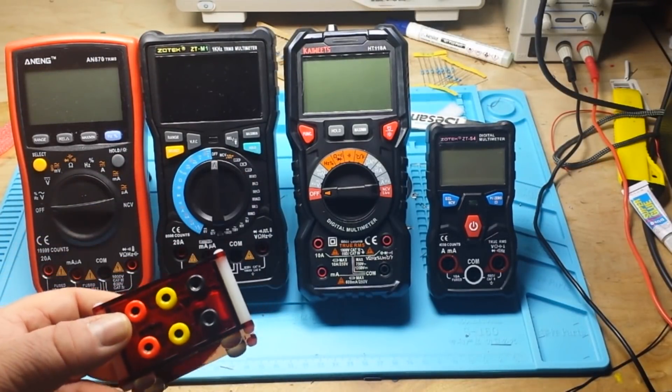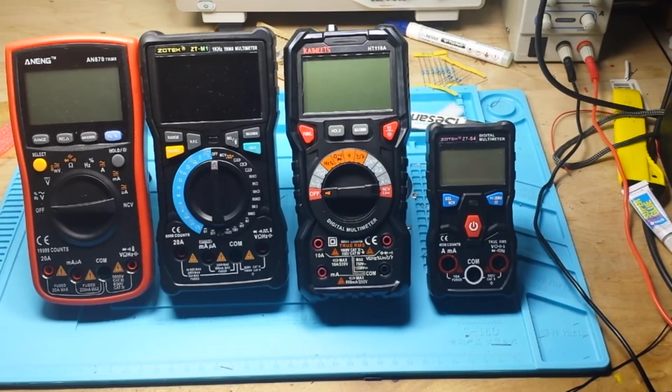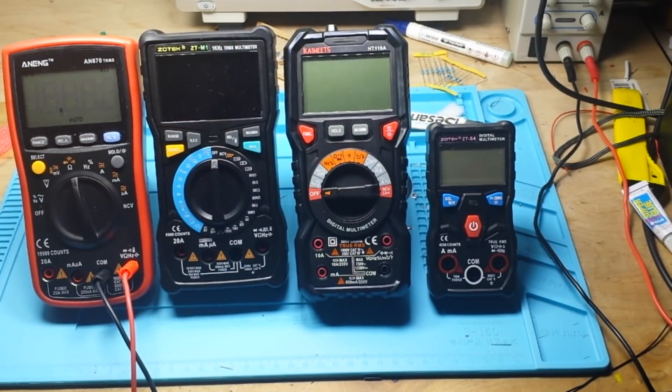The resistance is marked at either 179.95 or 179.999 kilohms depending on which test standard you look at. We'll start with the Aneng AN870 — and it says 180.1, so that's pretty bang-on close to what this device was calling for.